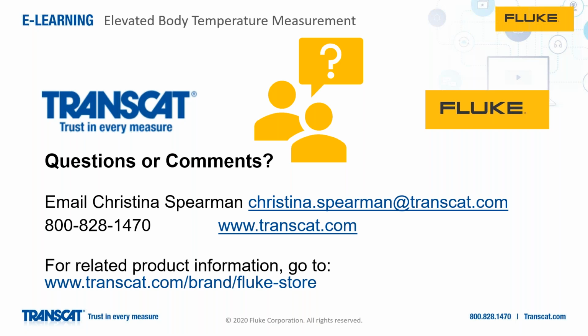It's got a very limited measurement temperature range, but very accurate within that range, to the 0.5 degree F that we talked about. When compared to an industrial thermometer like what Fluke has produced for a number of years, they're really intended for different applications, and their specifications aren't such that they can be used interchangeably. An industrial thermometer has a very wide temperature range and a much broader, or looser, accuracy specification, as it's intended for a different application.